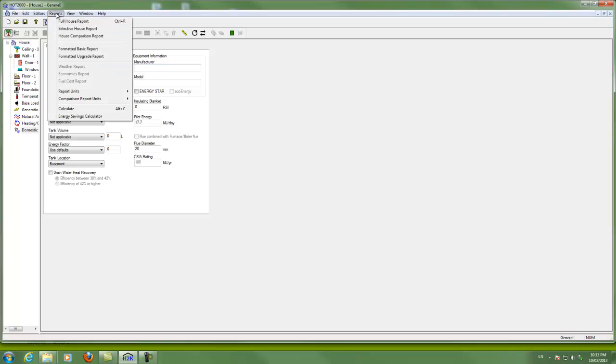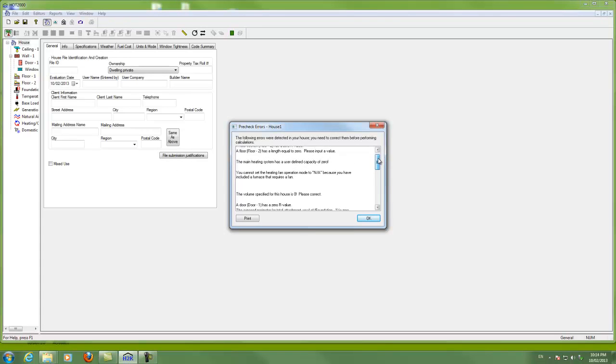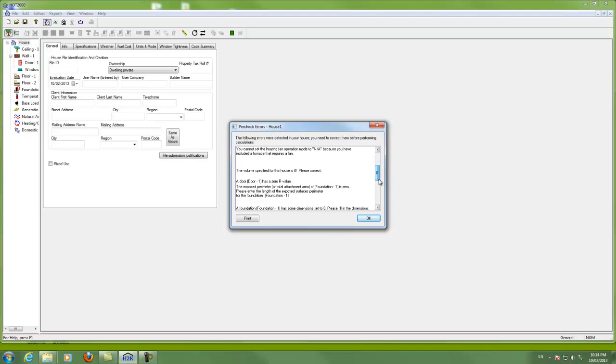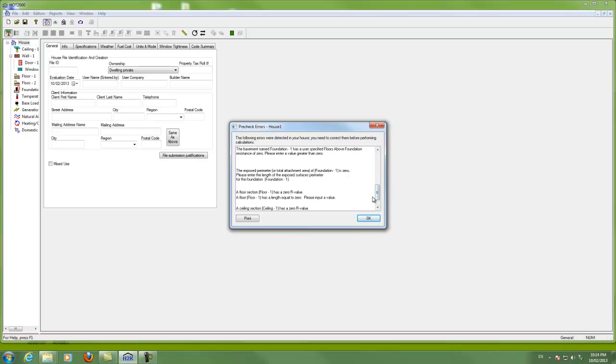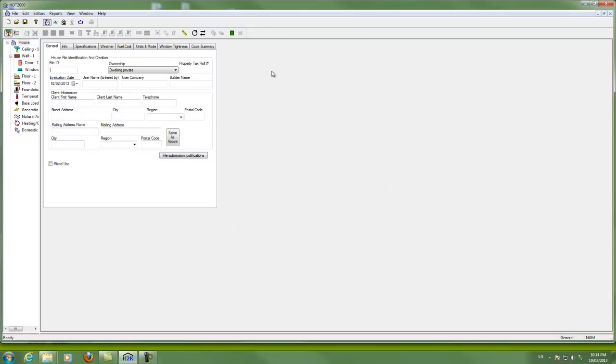Once you've got a house modeled, a good thing to do is to try to run a report. That's where your information that you're wanting to get is going to come from. And so you can try to run a full house report like this. And the first thing that will probably happen to you is you'll get a bunch of errors. So pre-check errors for house number one. So before the program will actually calculate anything for you, you're going to have to deal with these errors. And so I've got some walls and things with lengths equal to zero. And I've got R values that are unspecified. And those are mainly the errors, lots of them. And so if we had modeled a real house, hopefully we'd have little to few errors there. And we can tidy those up and carry on.